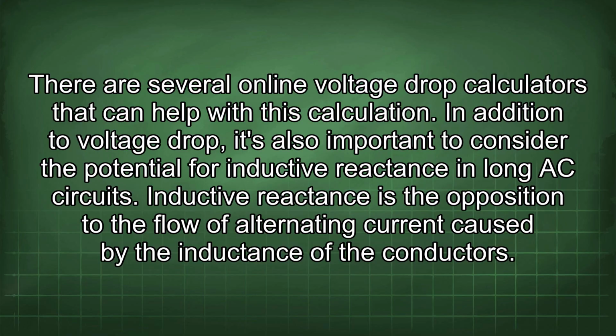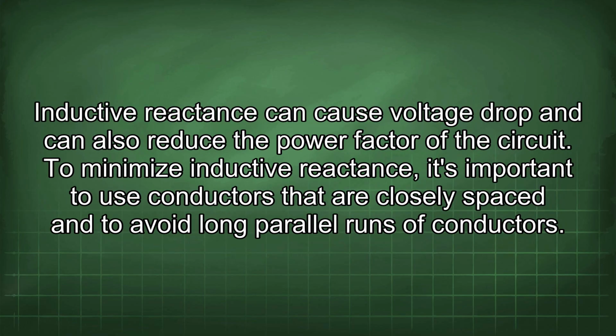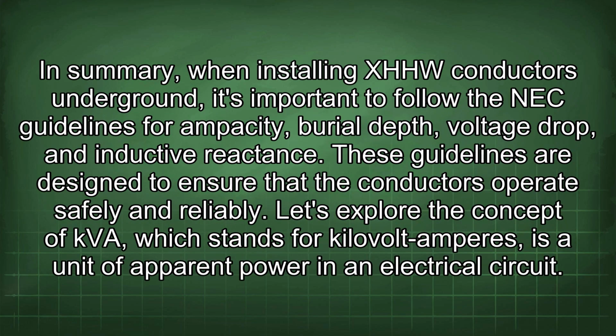In addition to voltage drop, it's also important to consider the potential for inductive reactance in long AC circuits. Inductive reactance is the opposition to the flow of alternating current caused by the inductance of the conductors. Inductive reactance can cause voltage drop and can also reduce the power factor of the circuit. To minimize inductive reactance, it's important to use conductors that are closely spaced and to avoid long parallel runs of conductors. In summary, when installing XHHW conductors underground, it's important to follow the NEC guidelines for ampacity, burial depth, voltage drop, and inductive reactance. These guidelines are designed to ensure that the conductors operate safely and reliably.